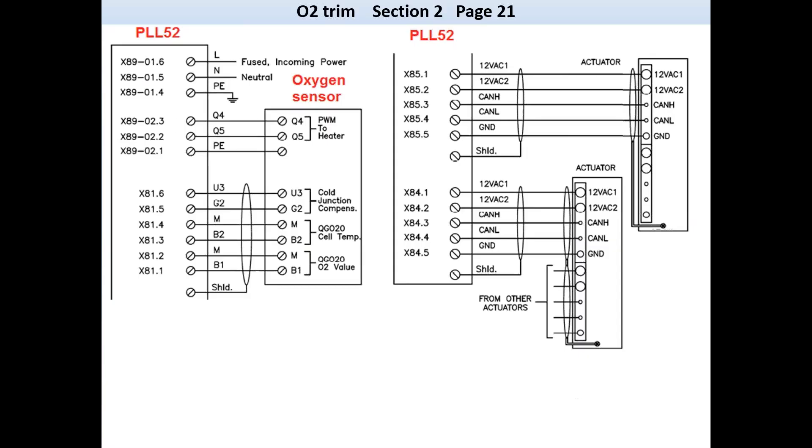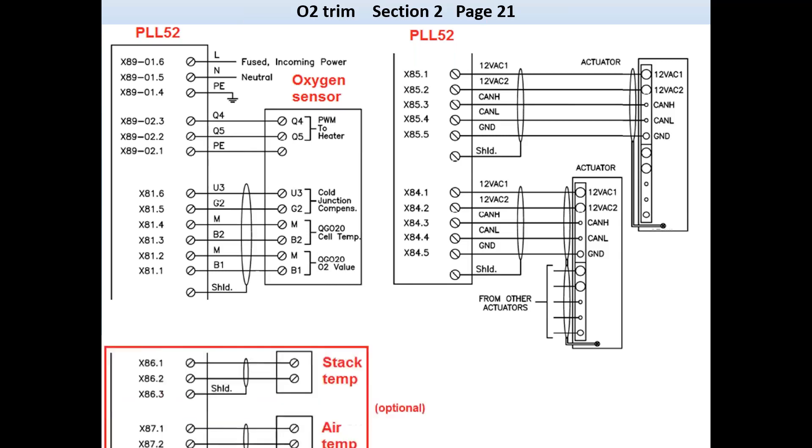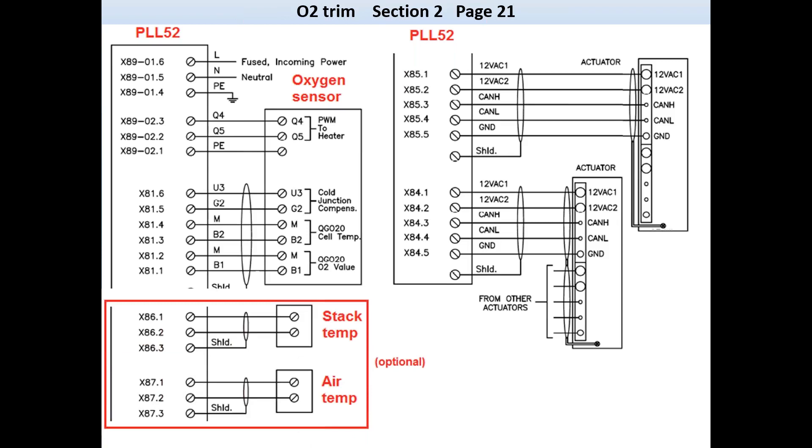The following slide covers the O2 trim connections. When doing O2 trim, a PLL CAN bus module is required, and obviously the oxygen sensor called the QGO. Not required, but usually supplied, are the ambient temperature sensor and the stack or exhaust flue gas temperature sensor. These two sensors allow the LMV-5, along with O2 level reading, to calculate and display burner efficiency. O2 trim is an investment, and the small adder for two RTDs is well worth the benefit of viewing the actual efficiency.